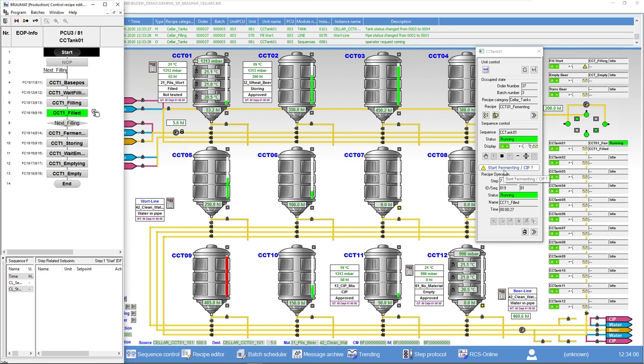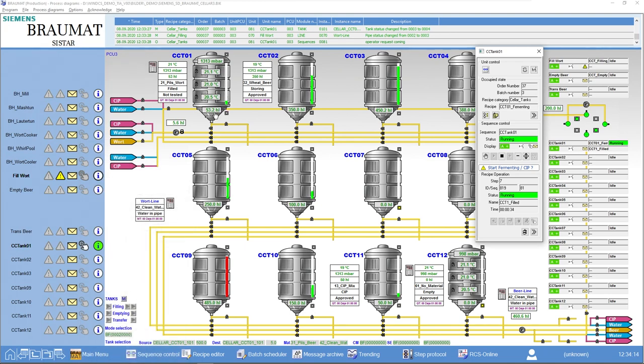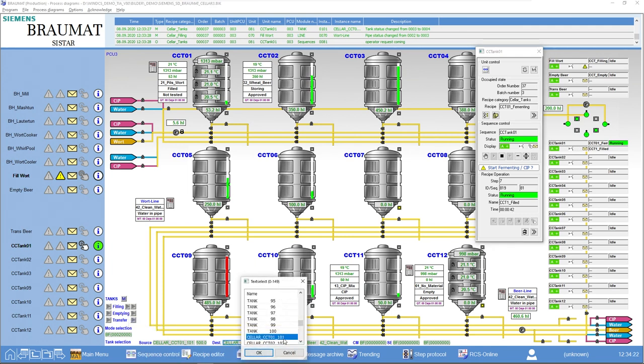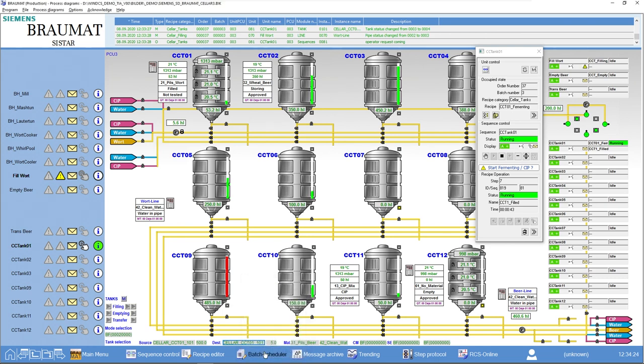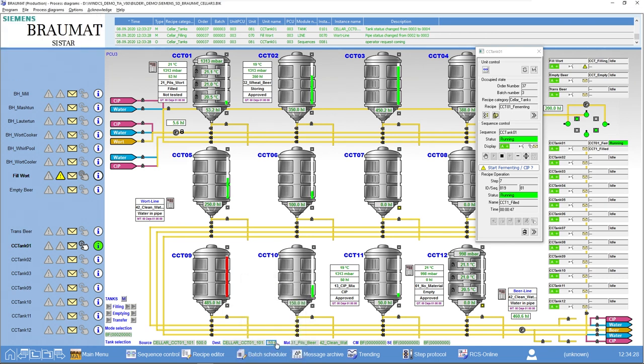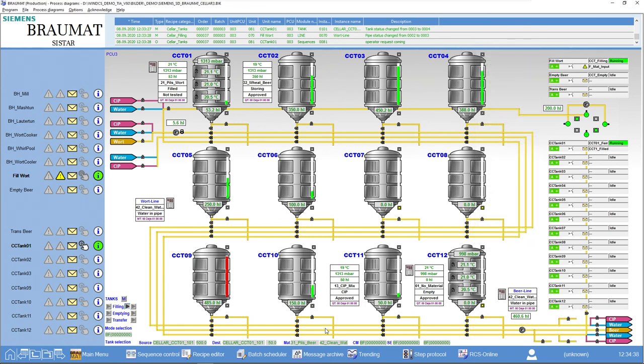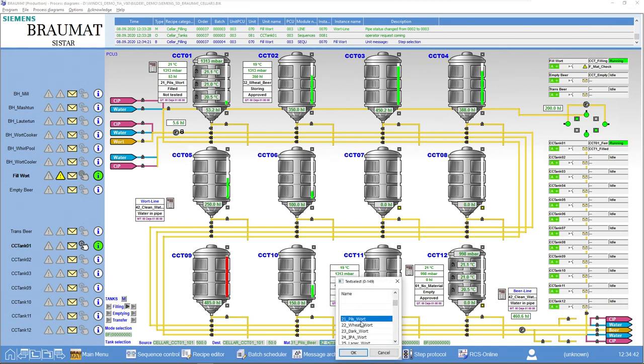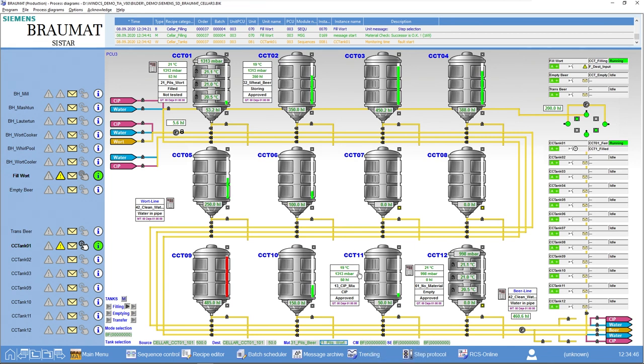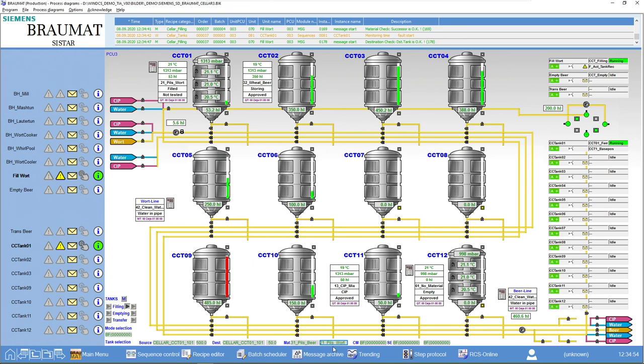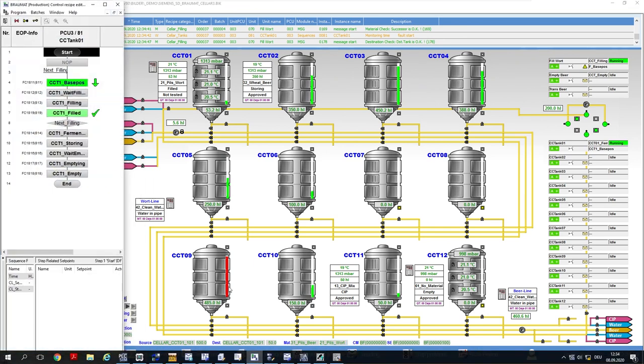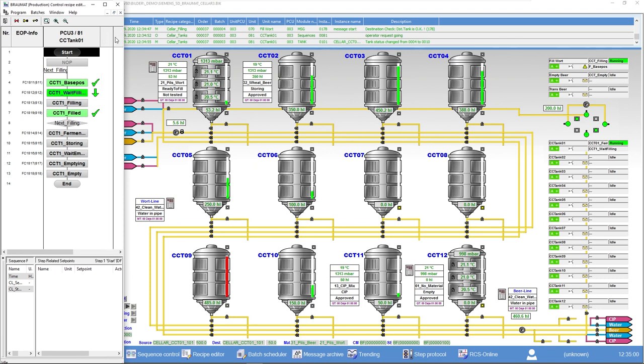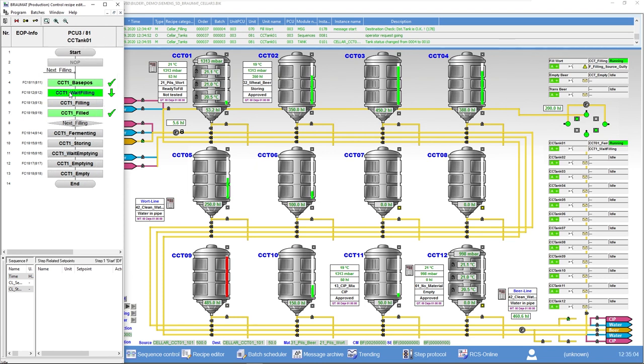On the one hand, I can now switch to fermentation. But I could also wait for another filling order to arrive. After all, the tank is nowhere near full. It holds 500 hectoliters. So I start a tank order again. This time I don't use the order system. I can also integrate it into the process image. There are no more queries about the material. The material has already been pre-assigned. The fill now worked. Here in the subsystem status field, we see the corresponding steps and my tank recipe continues accordingly. This is a loop. It has jumped back and is carrying out the second filling process.